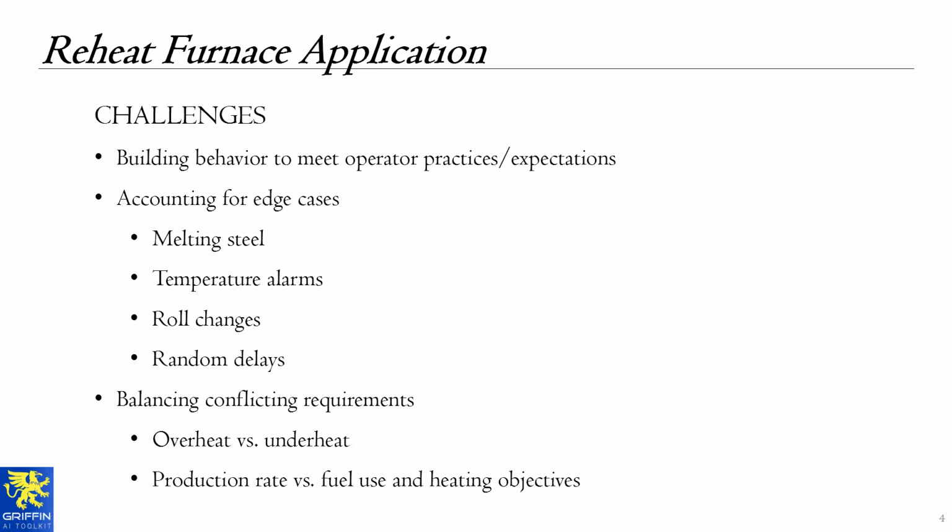Right now, they're having an issue. It's probably going to be our next project, where actually the pacing logic I was talking about, they're attributing basically too much process slowdown to that logic. And it could be happening. It could be that it's being overly conservative and holding things up when they could be putting more steel through. So we're going to have to take a look at that and try to find the ideal balance of maintaining required temperature as well as moving as much steel through the furnace as possible.